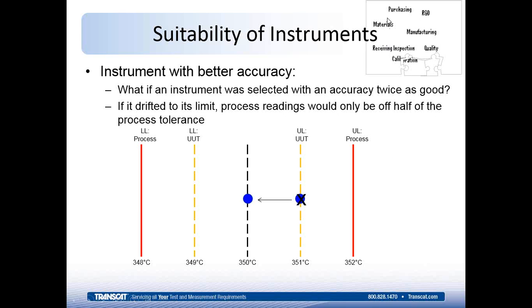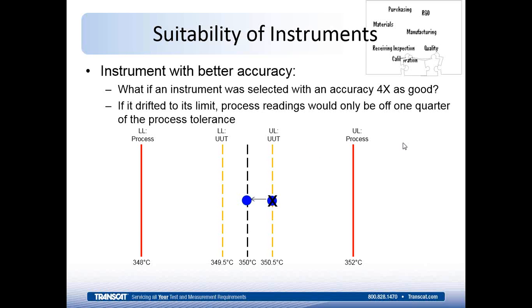So now let's select an instrument that has twice the accuracy of the process, or half the accuracy of the process tolerance. When it drifts now, you've got a little bit of room there. It would only be off half the process tolerance if it drifted the full tolerance of the instrument. And if we went 4 times as good for the instrument being used to measure the process, that would be a 4-to-1 process accuracy ratio. And this is why typically most companies go with a 4-to-1 decision. If you get towards a 10-to-1 or greater, then it gets to be pretty expensive for the standards. And you saw that from the example of the 4 instruments used for measuring that previous process. Your price of the instrument and maintaining it goes up. And so there's some optimal level there where you're keeping this risk of bad process measurements to a minimum, but not increasing your cost greatly.